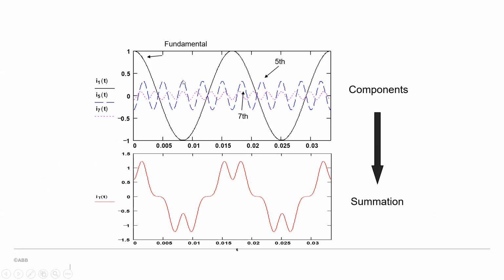If you see these harmonics, they add up, and the resultant waveform, although it should have been a pure sinusoidal wave like this, has got distorted because of this, and now the actual waveform looks like this. And because of this distortion, all these issues occur in the system.